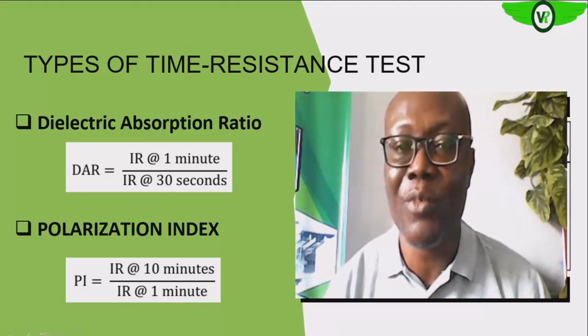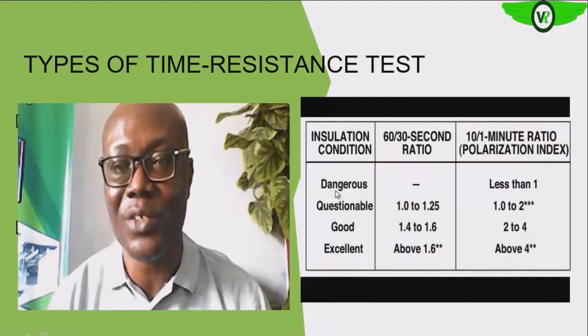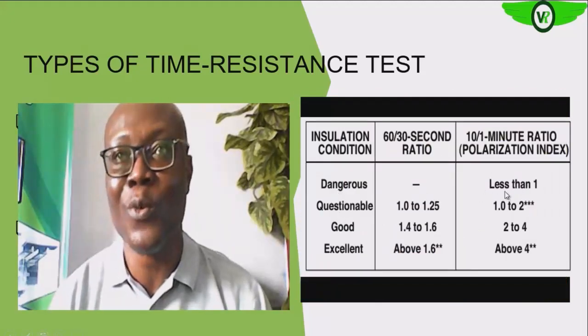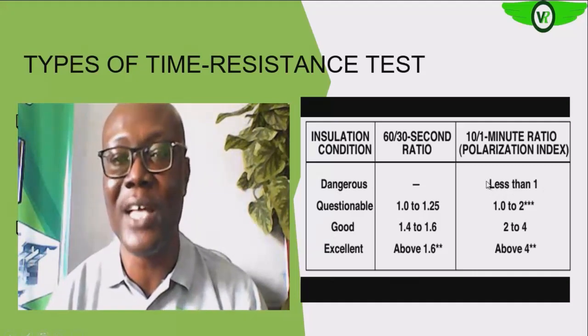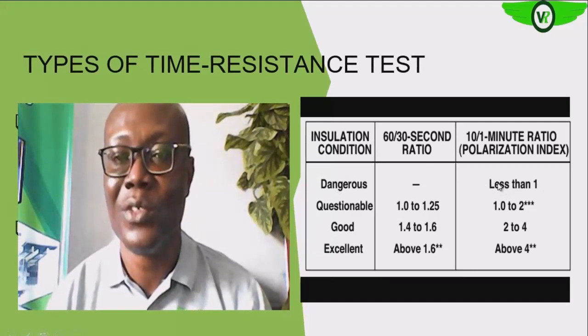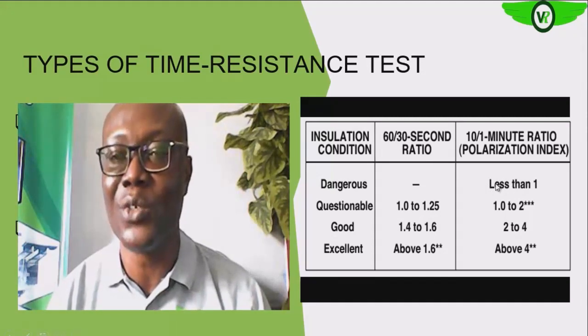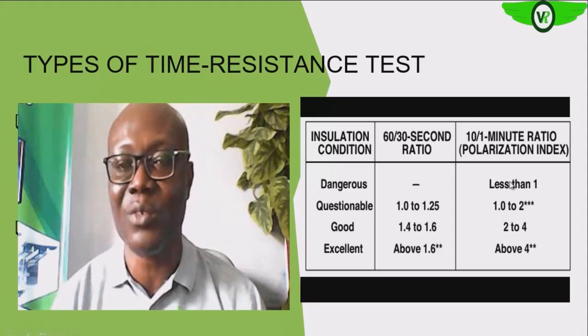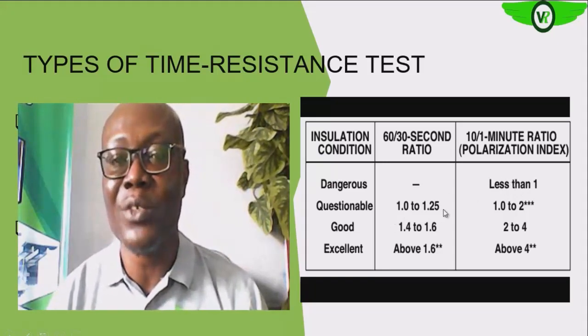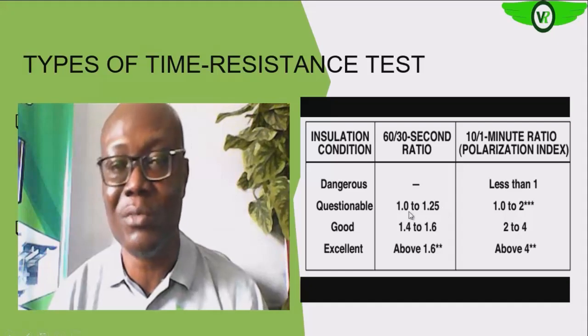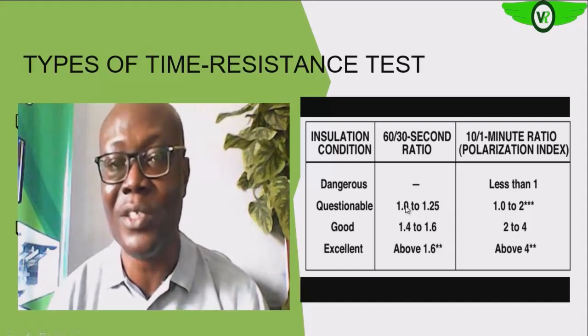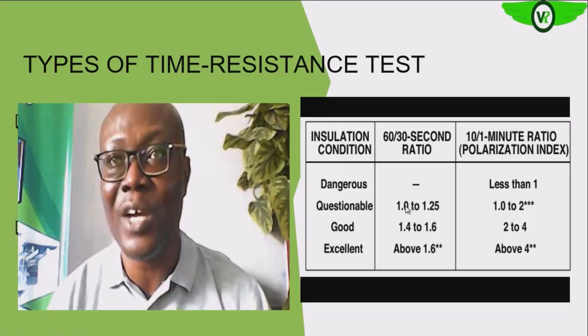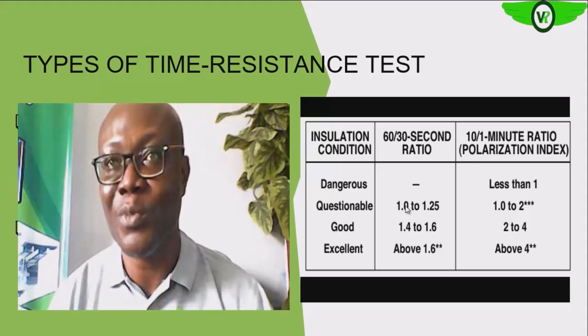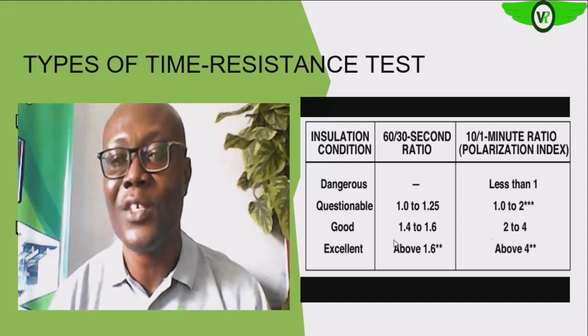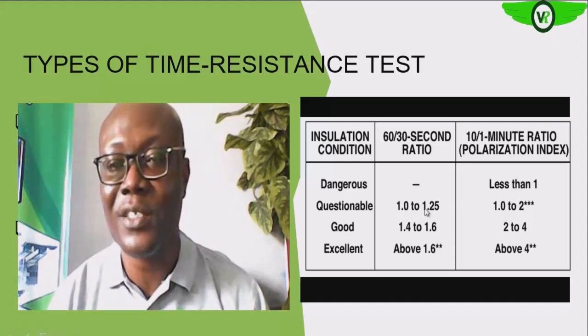So here are some of what is expected, or how to interpret the result. Anything less than 1 is a no-no. It's not acceptable at all. That's dangerous to the life of the equipment and also to the safety of personnel that will be working around. If it is between 1 and 1.2, like I said, if it is low voltage equipment, it could be acceptable, depending on the level of insulation IR value on each of the spot readings. So it is questionable.